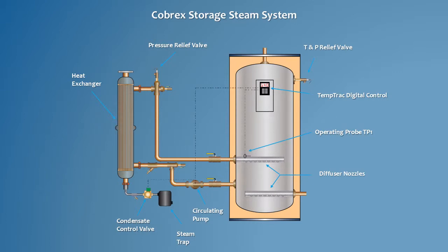The Cobrex storage steam system is designed to provide domestic hot water for potable uses. The energy source is district, municipal, or locally produced steam at pressures up to 125 psi. The water is heated in a heat exchanger package consisting of a heat exchanger, temperature-operated pump, and condensate control valve in conjunction with a storage package including a water storage tank, digital temperature control, and all related safeties in accordance with industry requirements and recommendations for potable water heating devices.